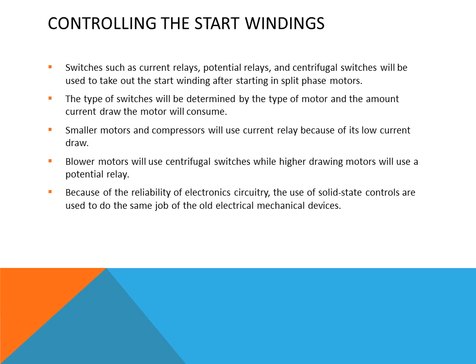Switches controlling the start windings — such as current relays, potential relays, and centrifugal switches — are used to remove the start windings after starting a split phase motor. The type of switch is determined by the motor and the current it draws. The start windings cannot stay in the circuit — if they did, it would damage the motor. Another type is the solid state switch or relay, which performs the same function as electromechanical devices but is more reliable since it has no moving parts and less to wear out.